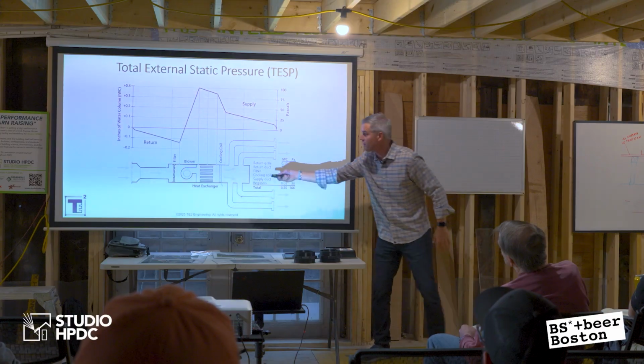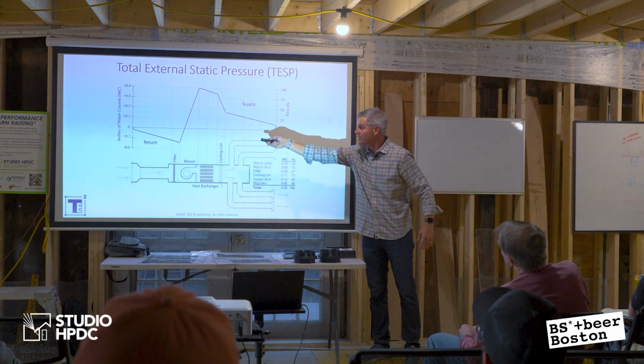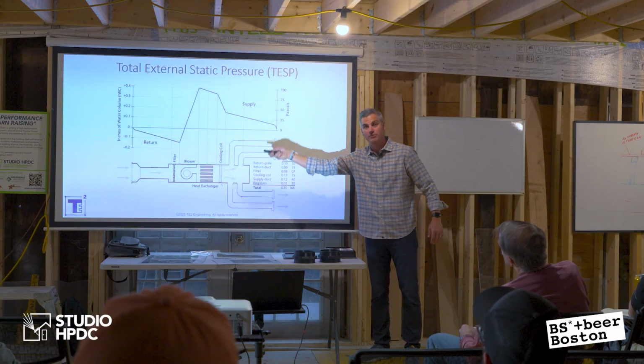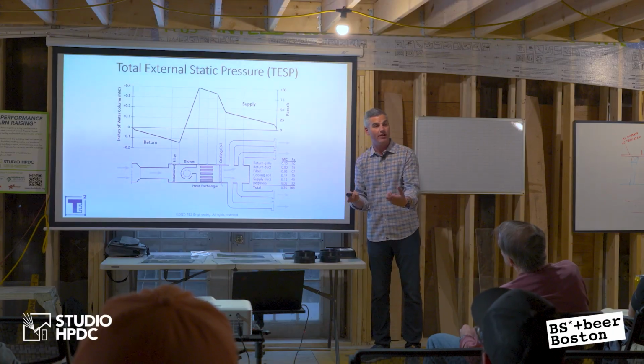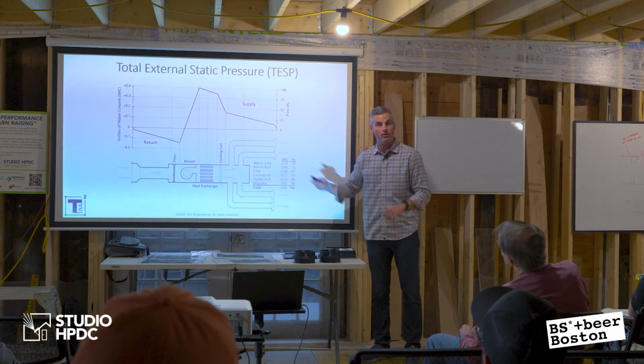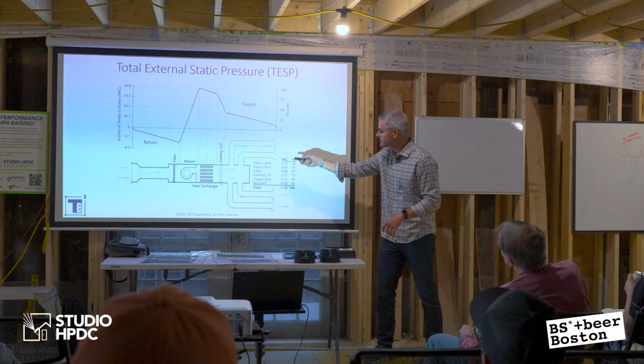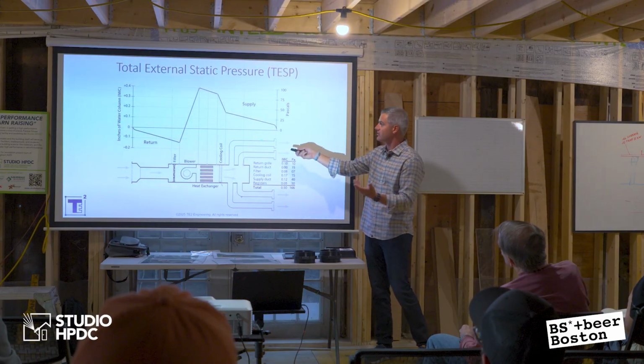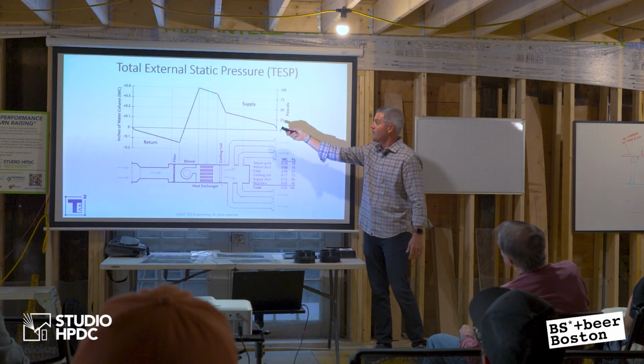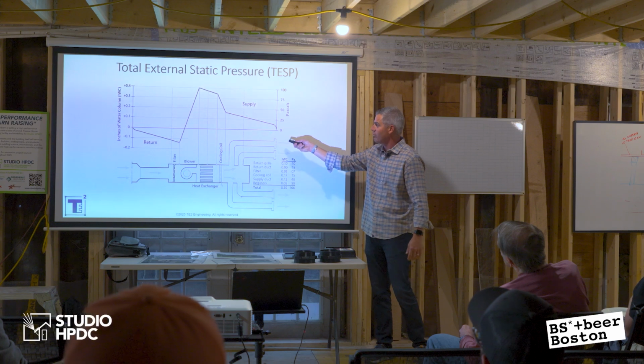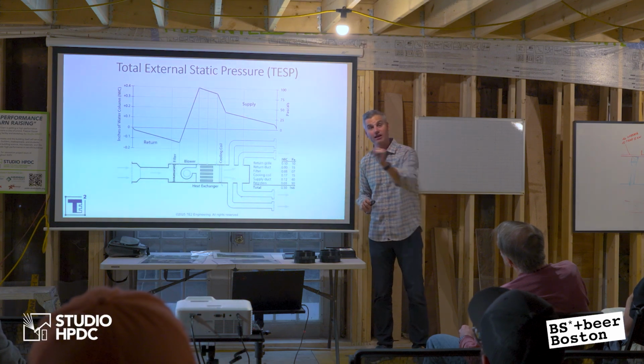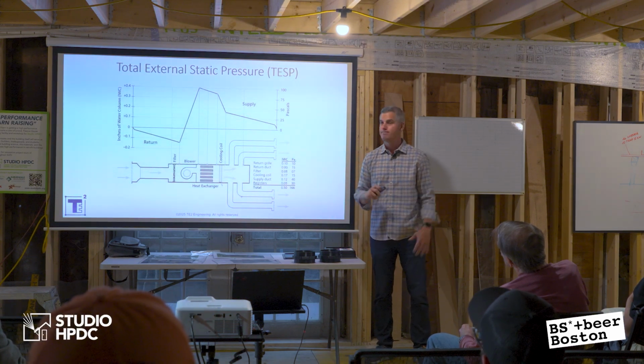So if you put in too restrictive of a filter, guess what? That drop right there is going to be massive. The filter drop is going to be too much. It's too much resistance on that air handler. The blower's going to struggle, right? If I put undersized ducting, if all this ductwork on the supply side is undersized, guess what? I'm not going to have enough oomph. It's going to cut out. It's going to cut down before I get there. I'm not going to get enough airflow into the room. Not enough CFM, right?